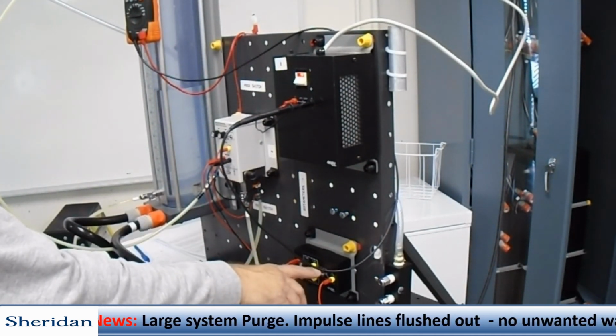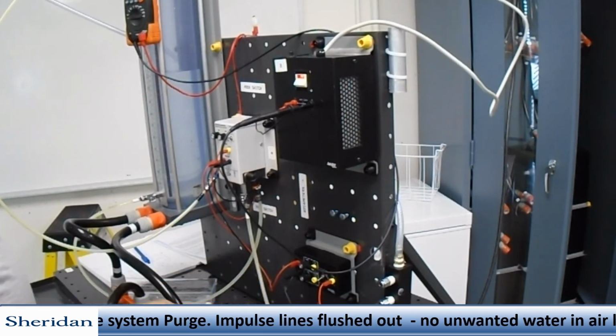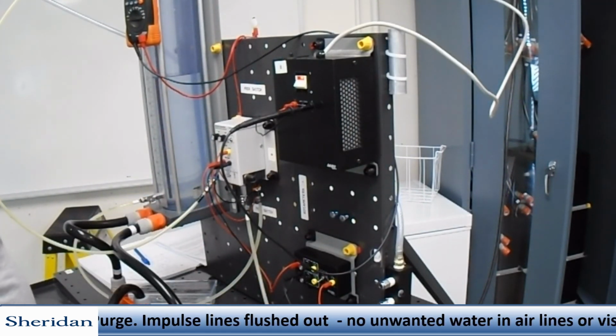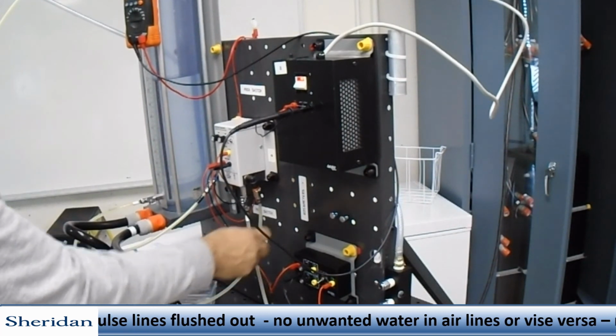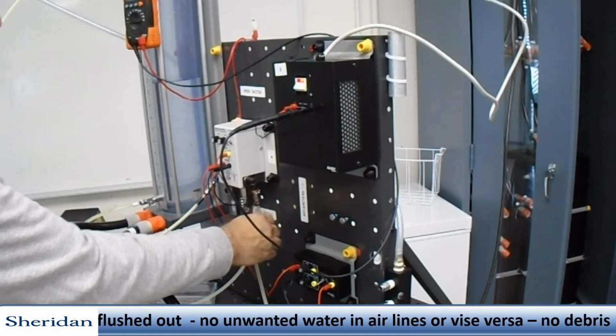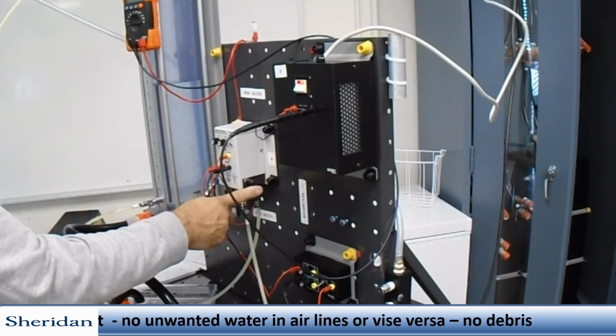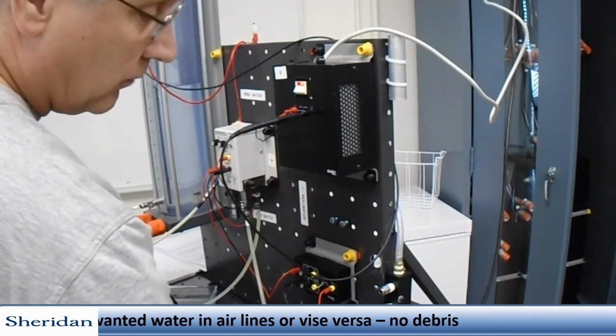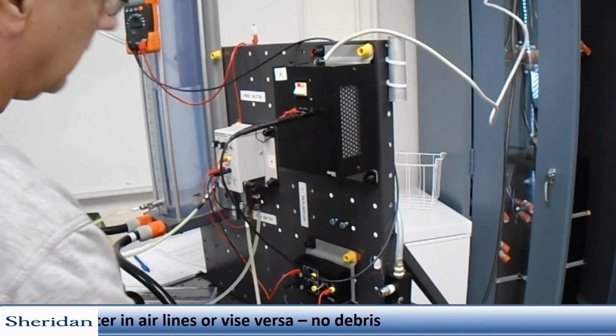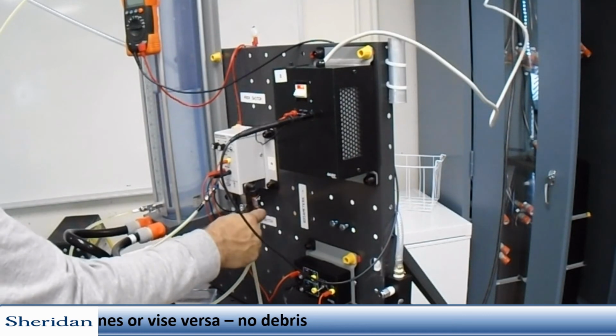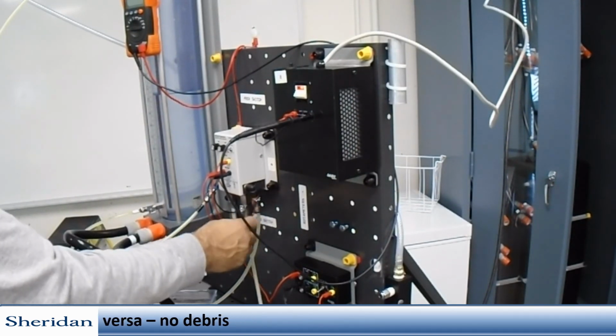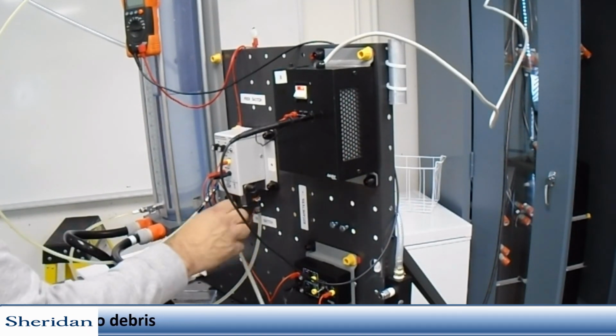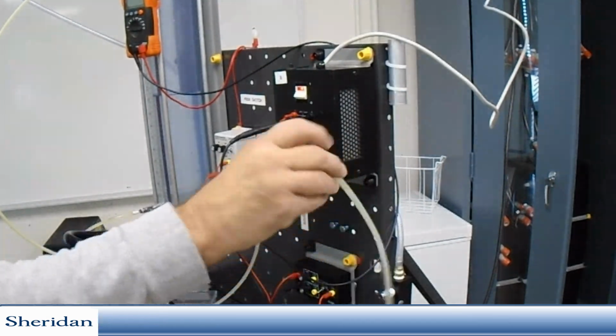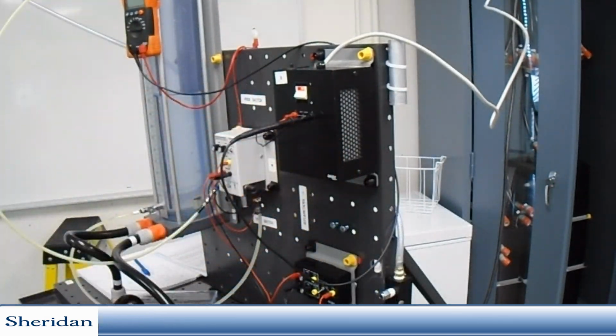As the water is starting to go through, I'm going to shut the air off or close the valve. So the water is trapped. Right now we have water in our high pressure port, and we have water draining out of the bleed off line. So that's taking all of the air out. Once you've bled that out, just snap that out, the check valve will close, and the impulse line will be clear.